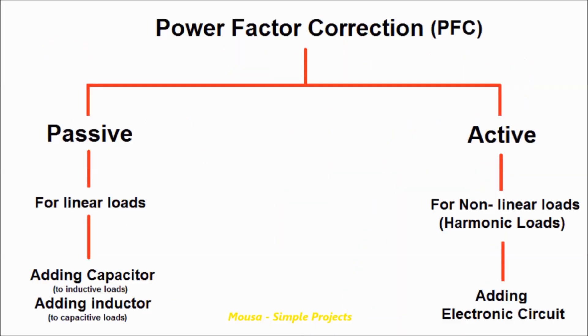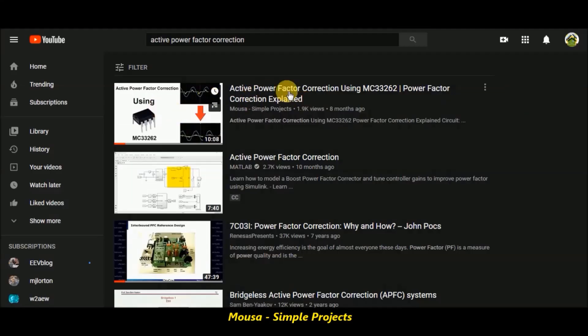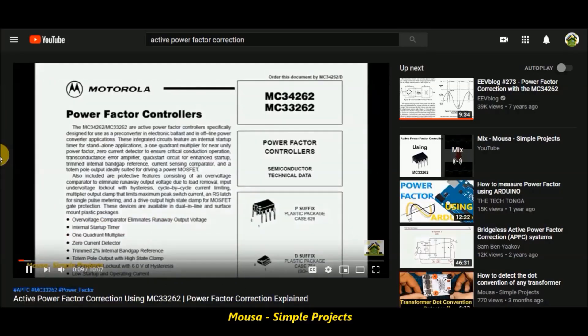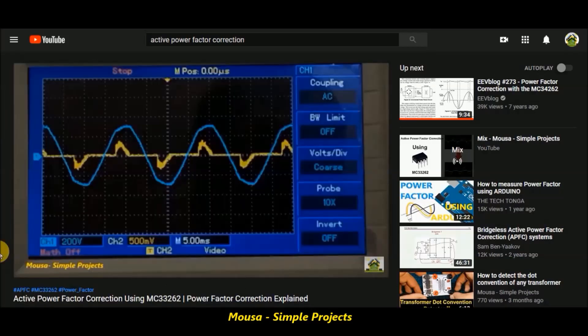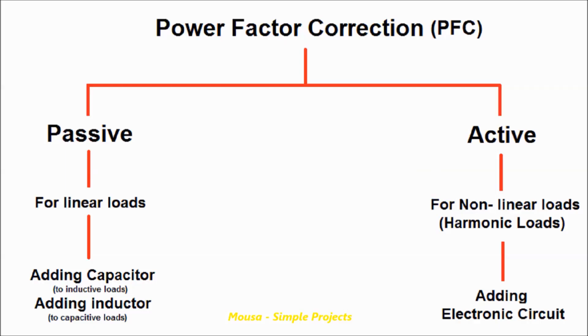There are two types of power factor correction: active and passive. Active power factor correction is used for non-linear or harmonic loads such as LED lamps, CFL lamps, and switching power supplies — I have a video about active power factor correction in my channel, link below in the description. In this video, I will explain passive power factor correction, which is used for motors and transformers and is usually done by connecting capacitors across the load.